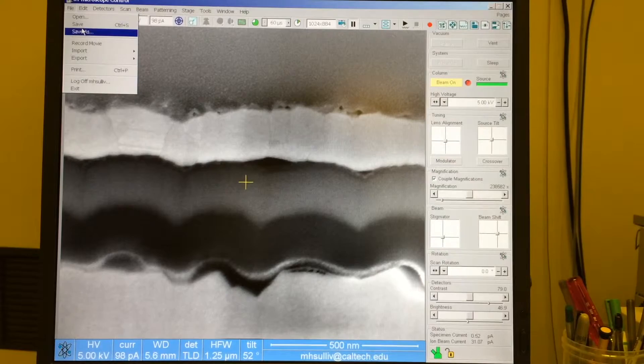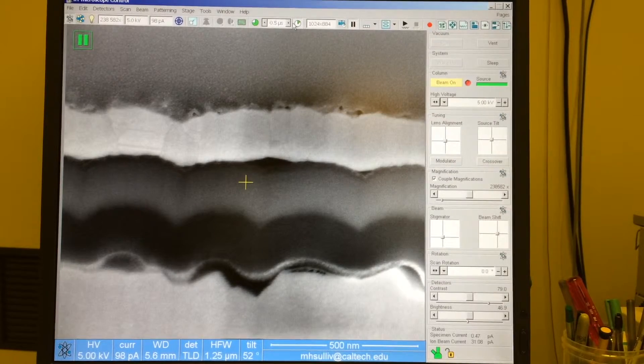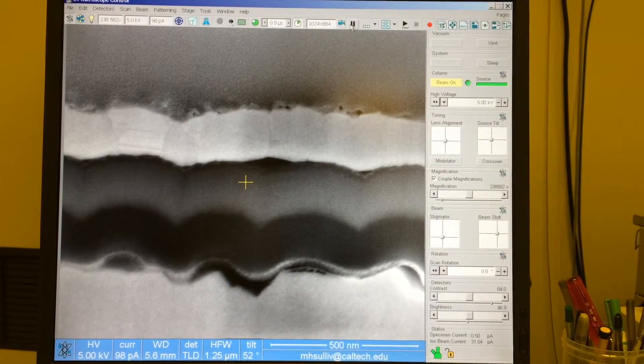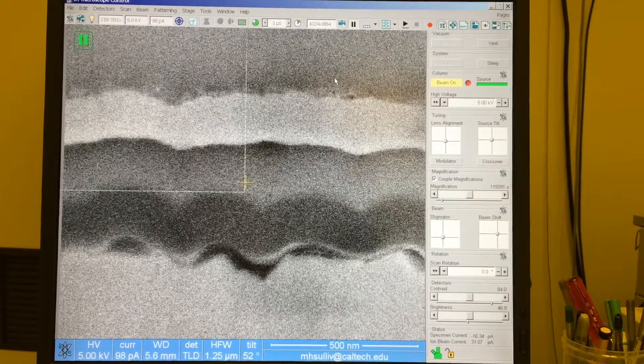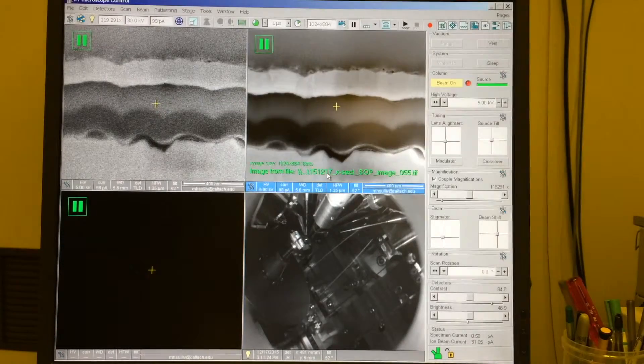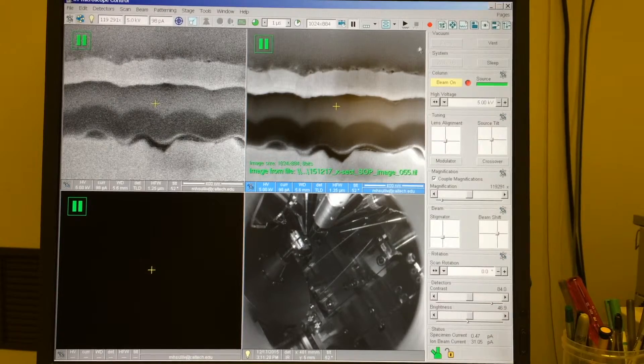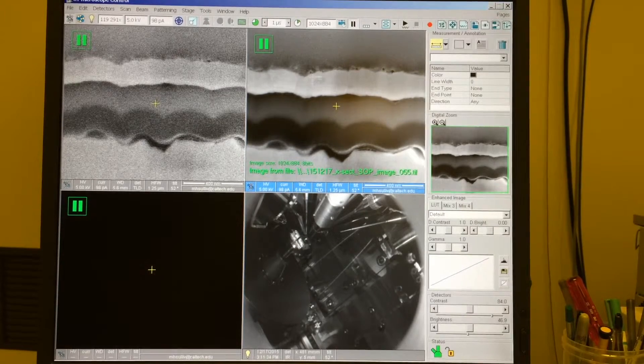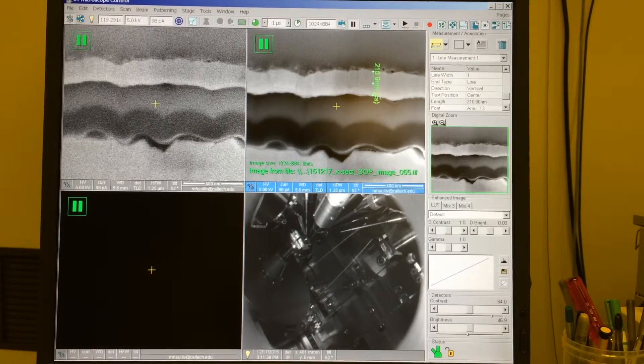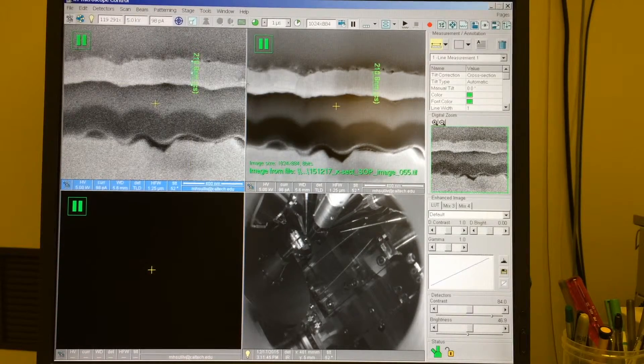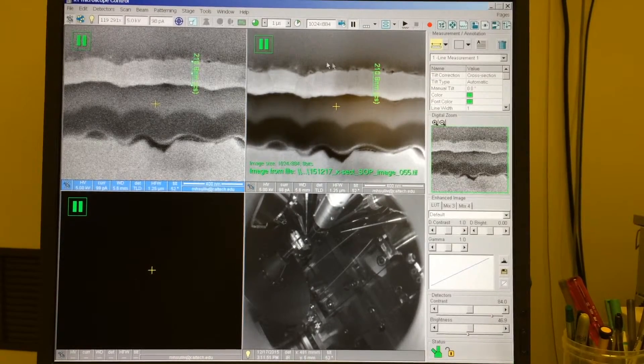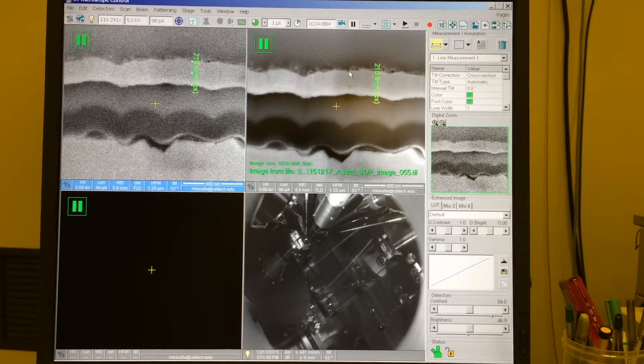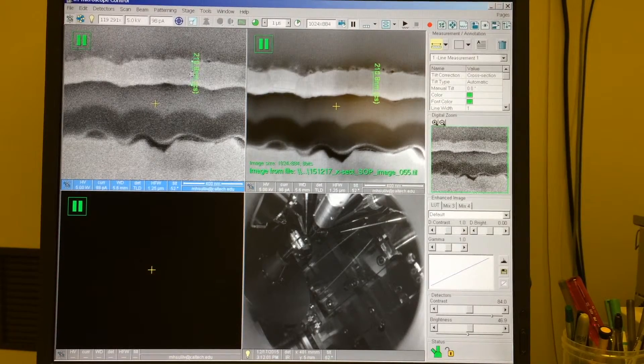And then what we could do is to check if we have that artifact. We can go back to a short dwell time and grab the same image, maybe at 0.5 or 1 microsecond, and pause that. And now if I recall the image that I just saved, we can compare the 60 microsecond dwell to the 1 microsecond dwell. On our measurement page, we can select a line measurement. And if I wanted to, I can measure the thickness of this top layer, about 210 nanometers, and compare that to the same spot over here. And so in this case, it actually seems like we don't have much stretching or shrinking of our layers, so we can trust the long dwell time image for our presentation or publication. But it's a good thing to check that to make sure that you're not unwittingly getting an artifact in your final image.